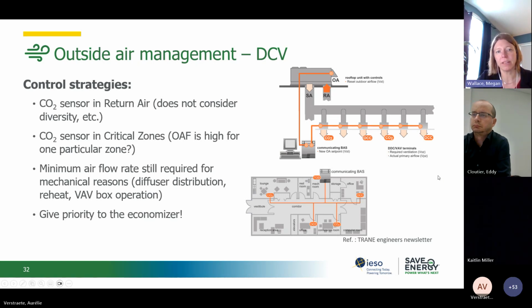The minimum airflow rate is still required, and you want to make sure that you have enough air for things like diffuser distribution, to make sure that the airflow patterns are correct, and reheat. The VAV boxes will have a minimum position as well. And in this case, always remember to give priority to the economizer. So in the right conditions, you'll have lots of outdoor air.